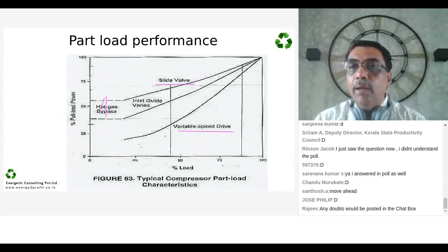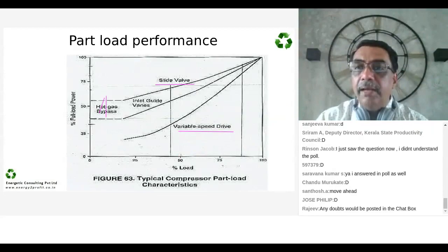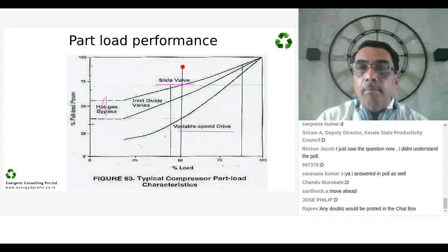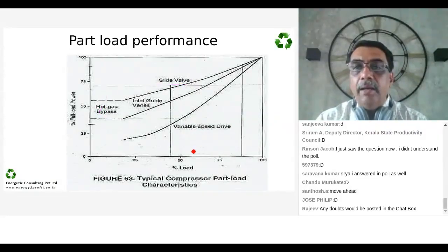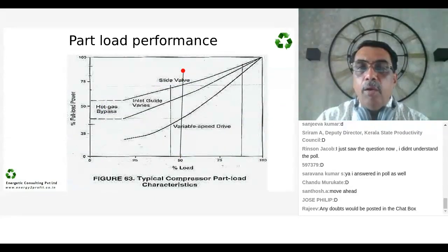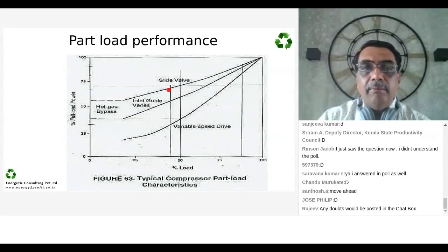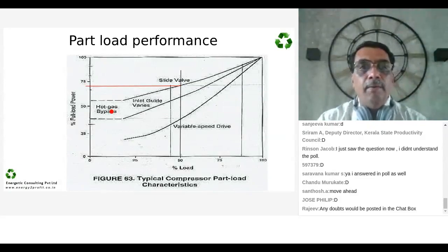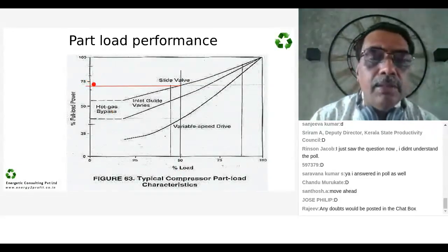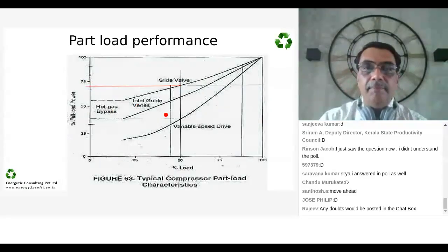What does it mean now? Let me take a loading of 50%. My 100 TR compressor is operating at 50 TR load. Capacity is half, that is 50% load, right? How does the sliding valve work at this point? At 50% load, it will consume something like 65% of energy. How does inlet guide vane control work?